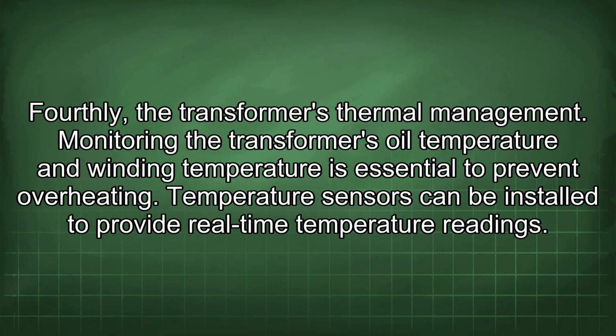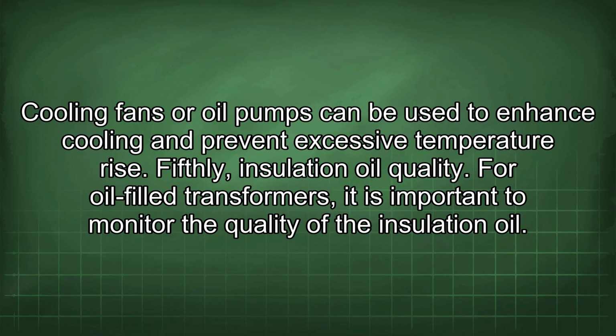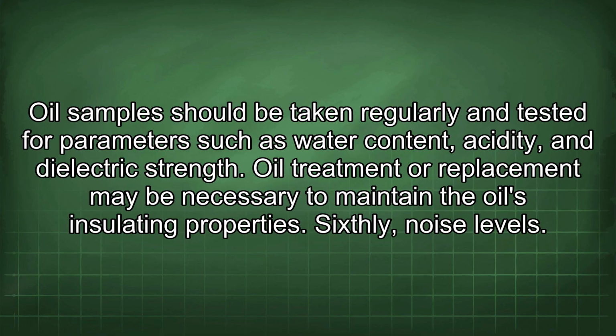Fourthly, the transformer's thermal management. Monitoring the transformer's oil temperature and winding temperature is essential to prevent overheating. Temperature sensors can be installed to provide real-time temperature readings. Cooling fans or oil pumps can be used to enhance cooling and prevent excessive temperature rise. Fifthly, insulation oil quality. For oil-filled transformers, it is important to monitor the quality of the insulation oil. Oil samples should be taken regularly and tested for parameters such as water content, acidity, and dielectric strength. Oil treatment or replacement may be necessary to maintain the oil's insulating properties.